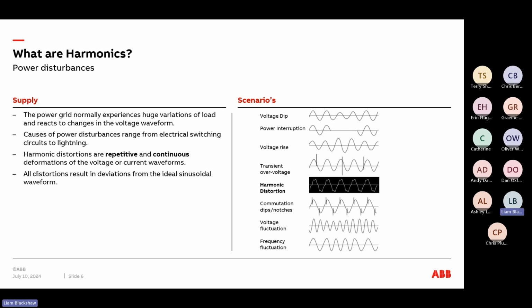You can see on the right hand side of this slide set that there are different scenarios where we have things like voltage dips, power interruptions, transient overvoltages, voltage fluctuation, and frequency fluctuation, where our frequency is slightly higher or lower than normal. But the one that we've obviously highlighted there is harmonic distortion. And harmonic distortions are what we class as repetitive but continuous deformations of the voltage or current waveform.